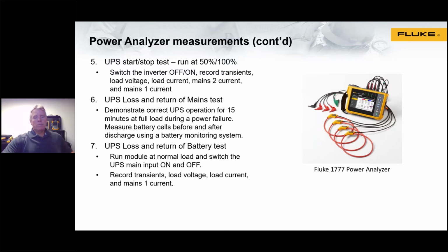Our next test will be a UPS loss and return of battery test. So you would run, again with our load bank, the UPS module at normal load, and then switch the UPS main input on and off. Again, what you're looking for there is evidence of transients, and also looking at load voltage, load current, and mains 1 current.